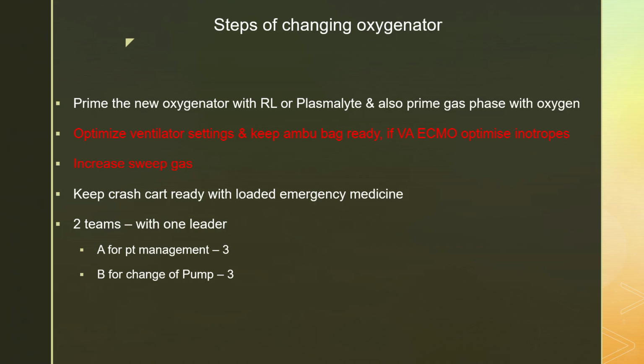Okay. Then when you need to change it, it is our double clamp method. We are going to show you how to do the double clamp method. You have to put 2 clamps before the component which you want to change. Suppose you want to change this, you have to put 2 clamps here, you have to put 2 clamps here, and then you have to cut the tube. Okay. So that is how we are going to change the components. Put double clamps, 2 before and 2 after. Remove it, take the new pump and connect it. Okay. So at least 3 people will be required to do this.